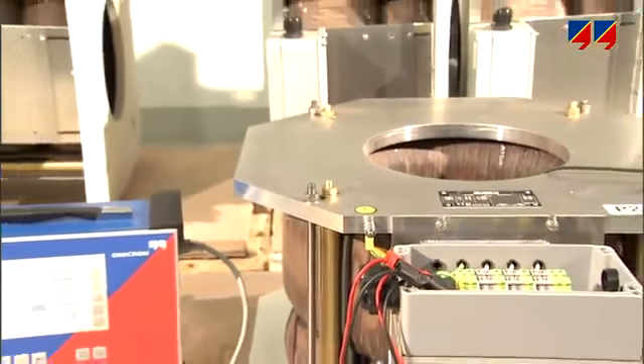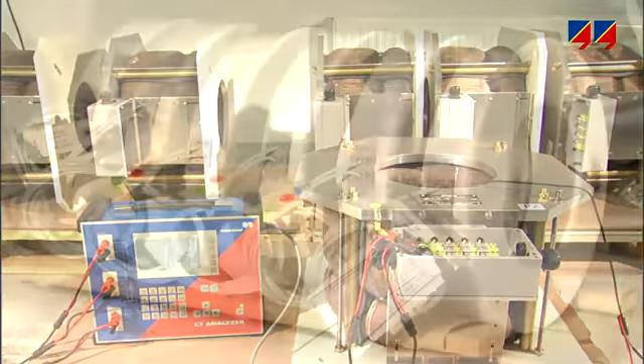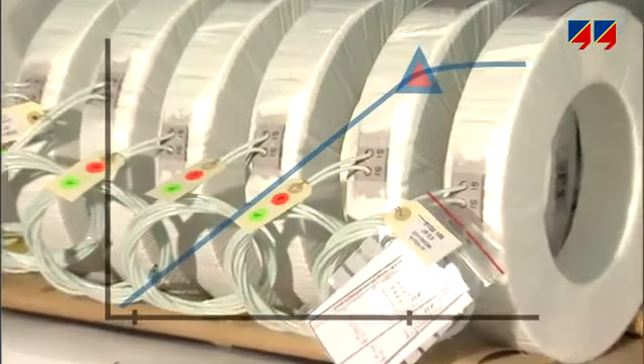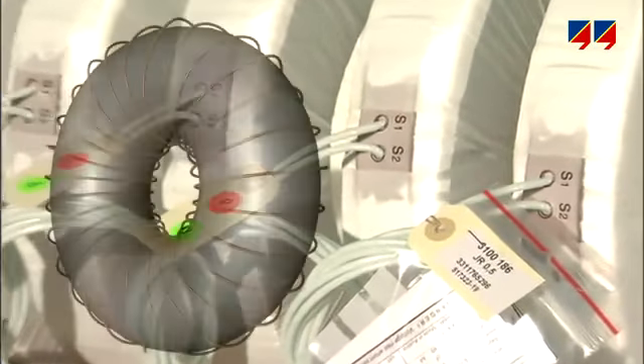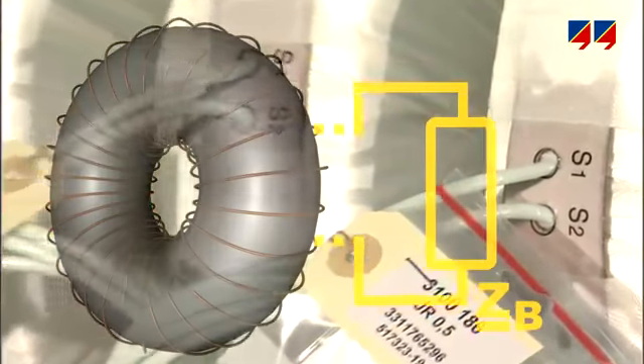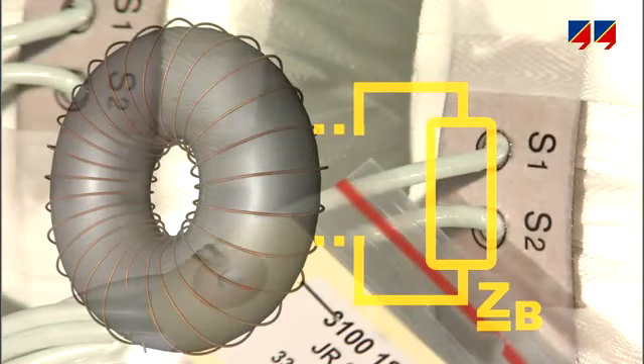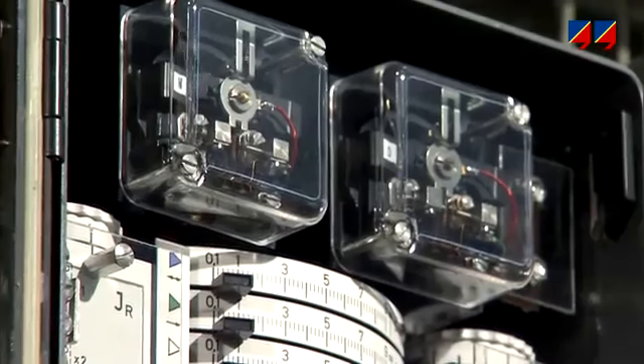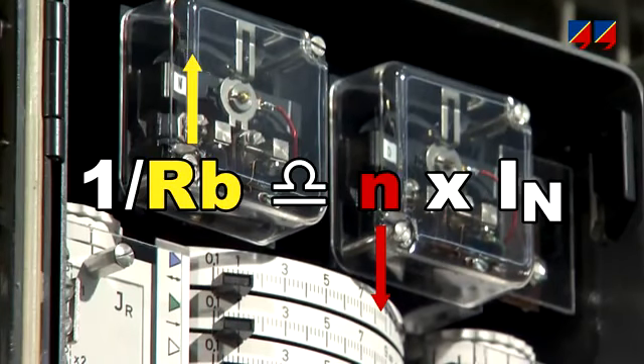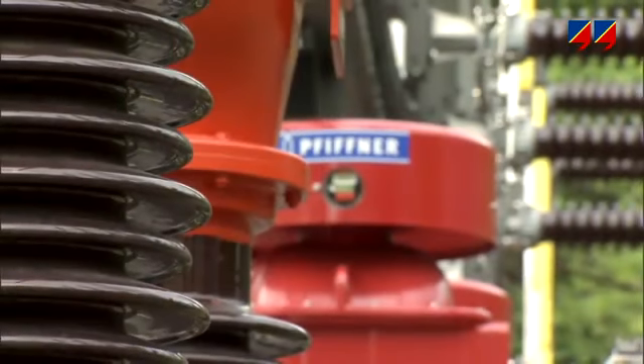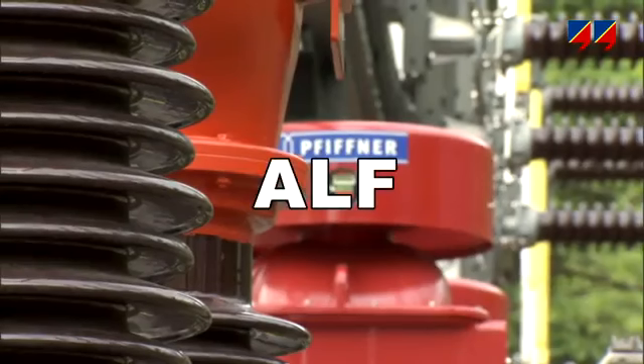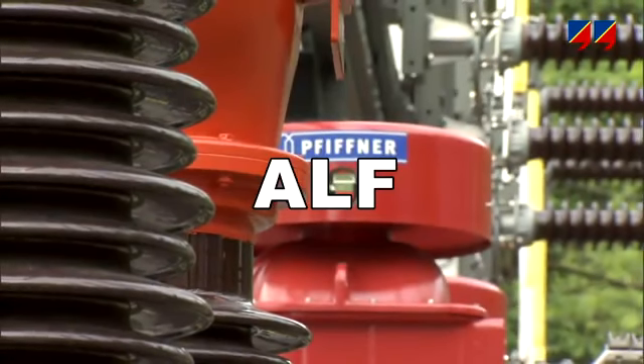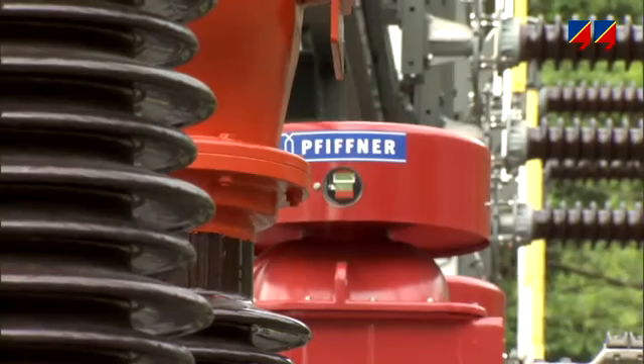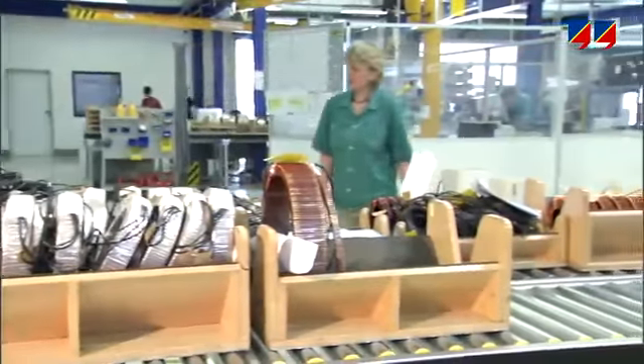Thus, besides the ratio, the essential characteristics of a typical protection CT are its knee point voltage and magnetic characteristic, its winding resistance, and the relation of its nominal burden to its actual burden as it directly influences a CT's performance. The higher the burden, the less current the CT can supply to the protection relay without saturating. Magnetic characteristic and burden determine the CT's accuracy limiting factor, or ALF, according to IEC 60044-1 and -6. Manufacturers verify these parameters during design, manufacturing, and acceptance testing.